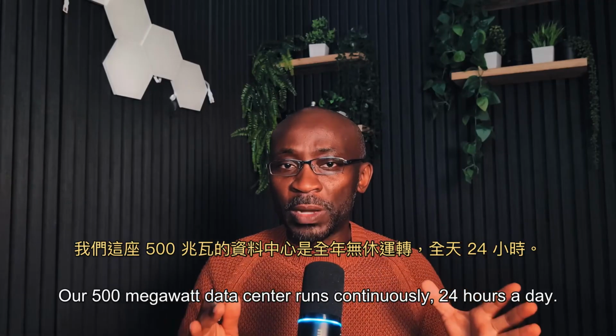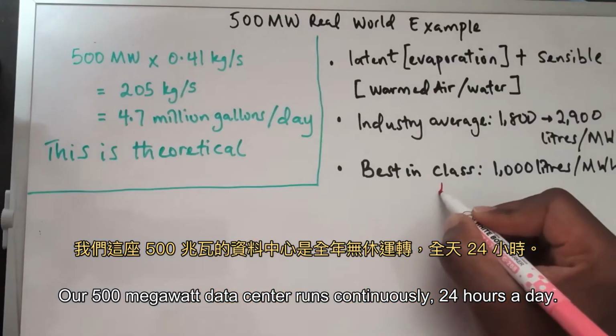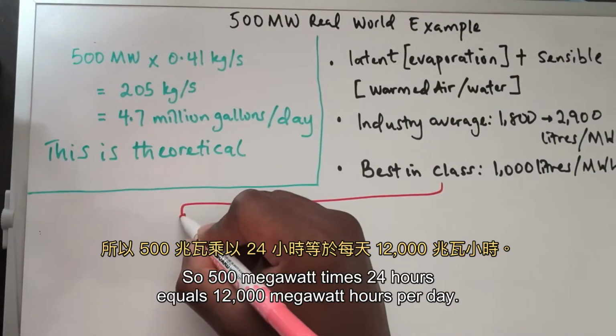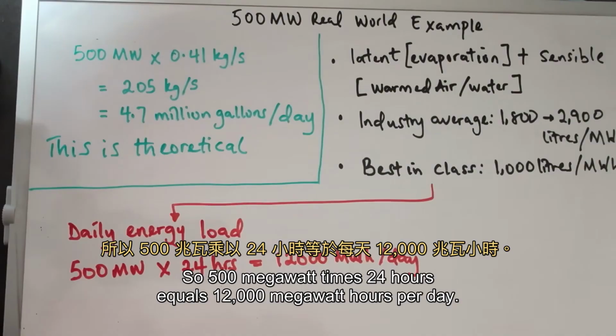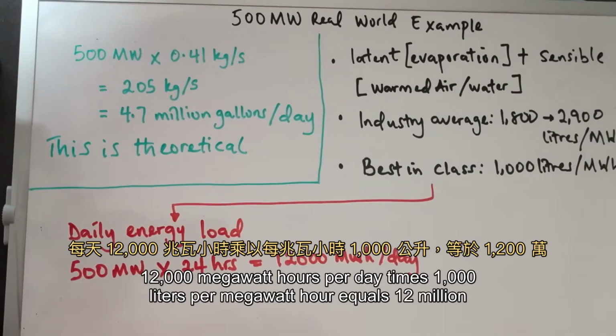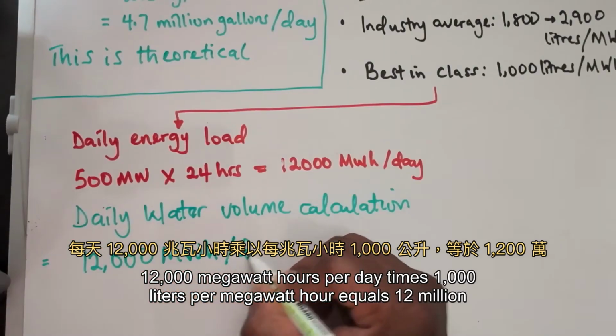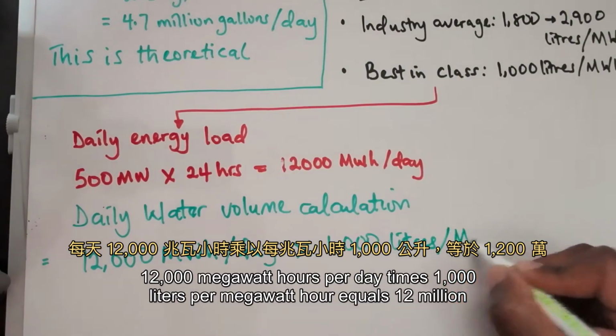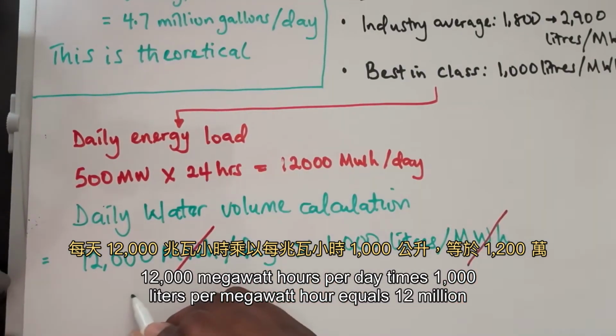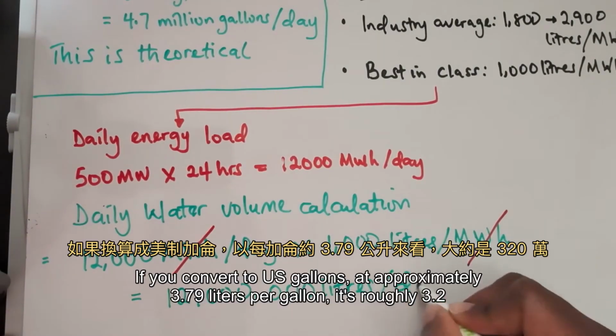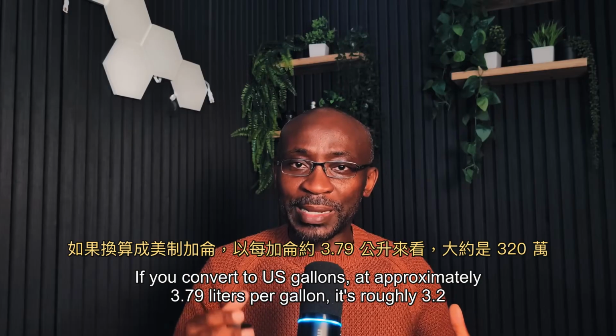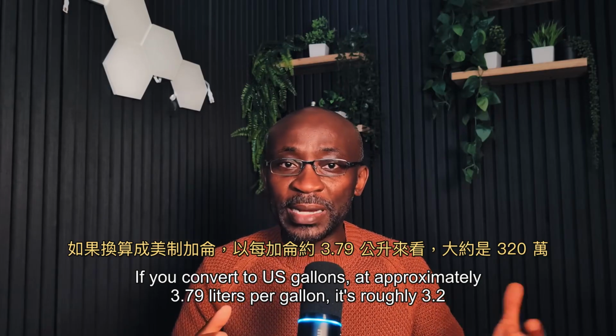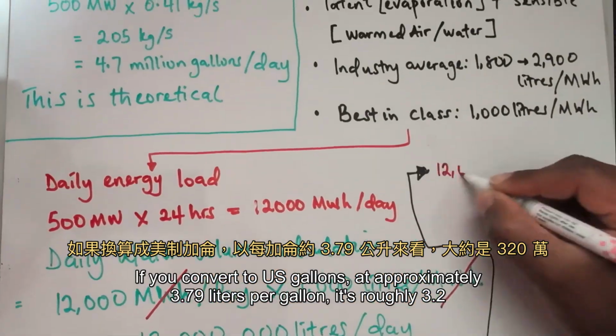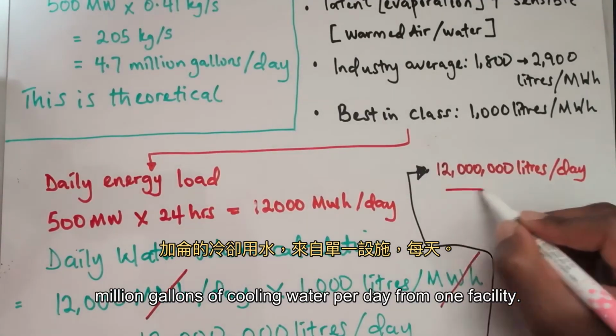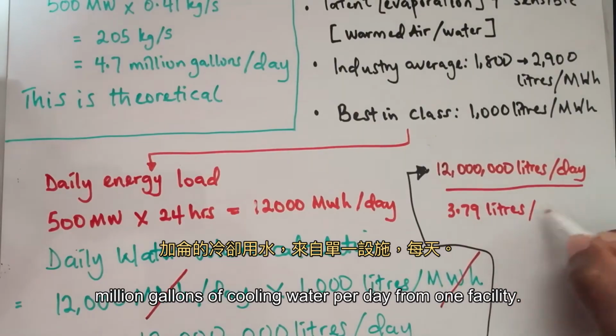Our 500 megawatt data center runs continuously, 24 hours a day. So 500 megawatt times 24 hours equals 12,000 megawatt hours per day. 12,000 megawatt hours per day times 1,000 liters per megawatt hour equals 12 million liters per day. If you convert to US gallons at approximately 3.79 liters per gallon, it's roughly 3.2 million gallons of cooling water per day from one facility.